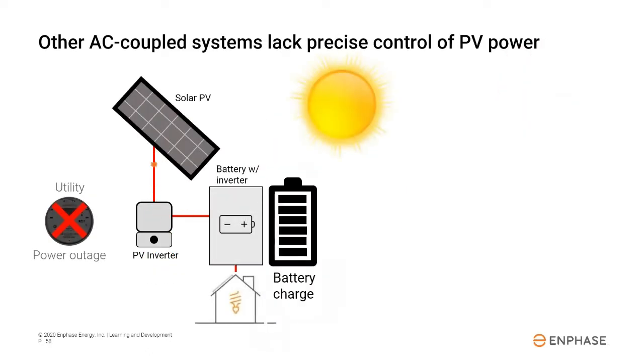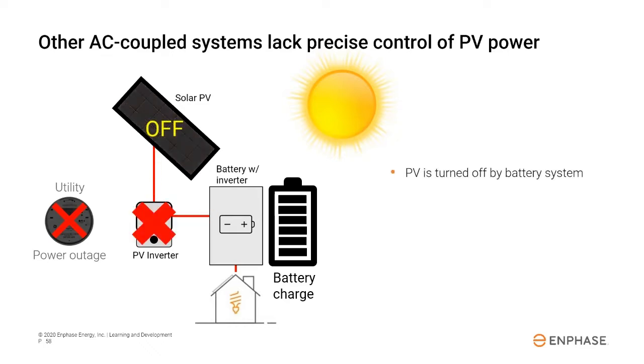Typical AC coupled systems curtail solar PV power by sending a crude signal to the solar inverter called frequency shift. This is interpreted by the solar inverter as an unstable utility grid, and the response of the inverter is to turn off. The problem with this approach is that with the solar PV system shut down, the battery is the sole source of power, and it's going to begin to drain. Once the battery's state of charge goes down to a certain level, the solar will be allowed to turn back on.